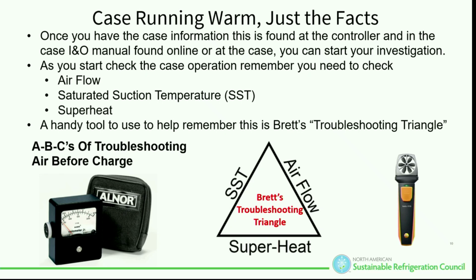I had an instance where someone said that the airflow was good, and the next technician went there with a anemometer the next day, checked the airflow, and the airflow was actually running 360 feet per minute on a case that was supposed to be only running 180. It was running double the amount of airflow. And essentially the symptom that he had was that the SST was way too high. It had like a 5-pound pressure drop within the system.